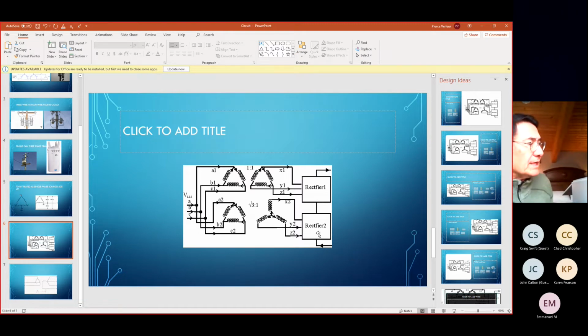Excuse me. The transformer itself is different from the power pole transformer. This is an additional device that you add in. And it's going to be big because the power runs through it. So it's going to be sized for the power, and therefore vary in size the same way the drive varies in size and the same way the motor varies in size. From a mass standpoint, you're going to have about the equivalent amount of copper and iron as the motor itself. So it kind of gives you an idea of the size of the device you're dealing with.